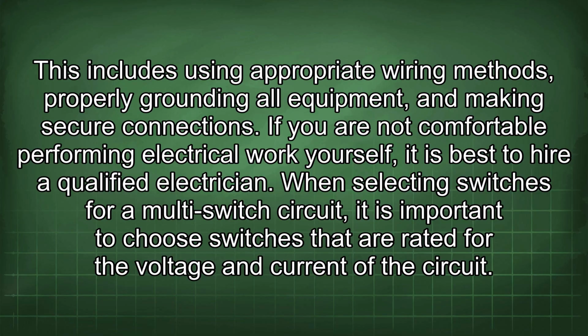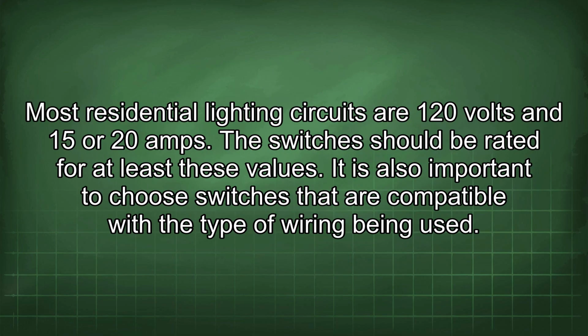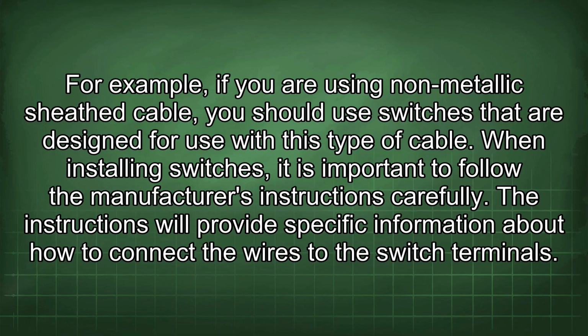When selecting switches for a multi-switch circuit, it is important to choose switches that are rated for the voltage and current of the circuit. Most residential lighting circuits are 120 volts and 15 or 20 amps. The switches should be rated for at least these values. It is also important to choose switches that are compatible with the type of wiring being used. For example, if you are using non-metallic sheath cable, you should use switches that are designed for use with this type of cable.